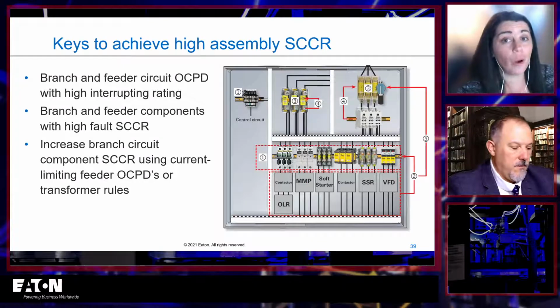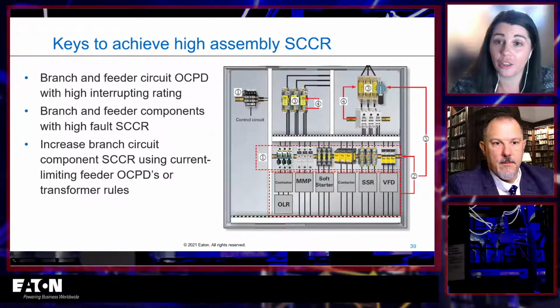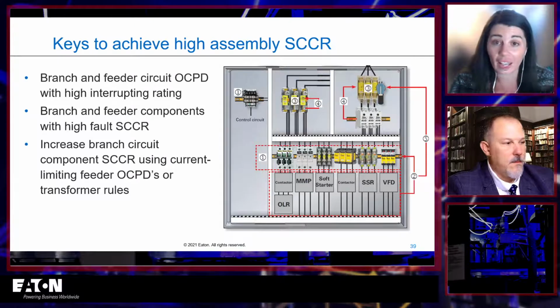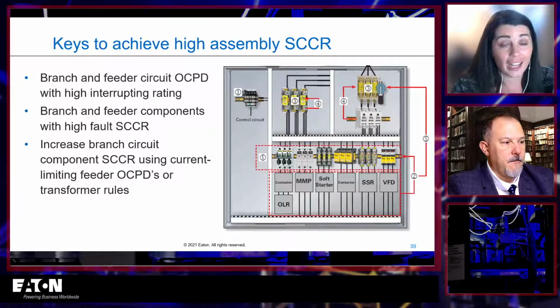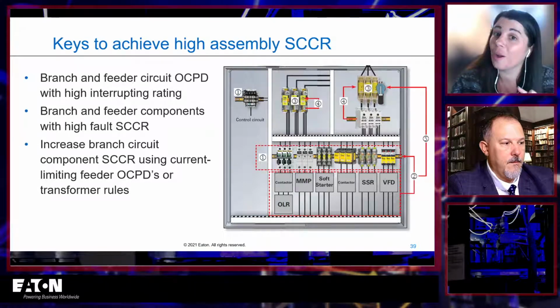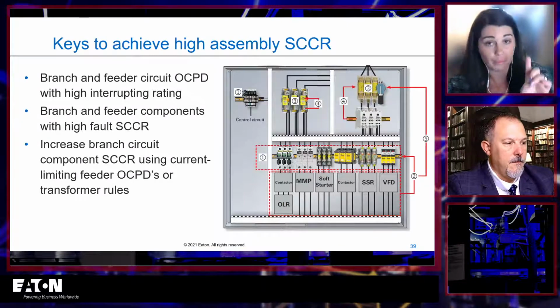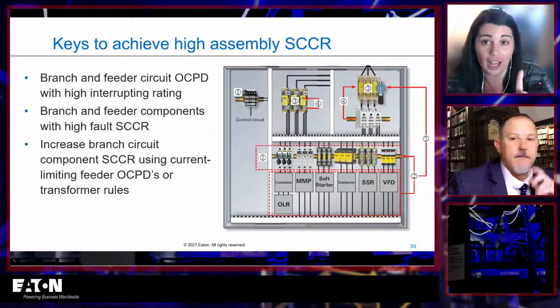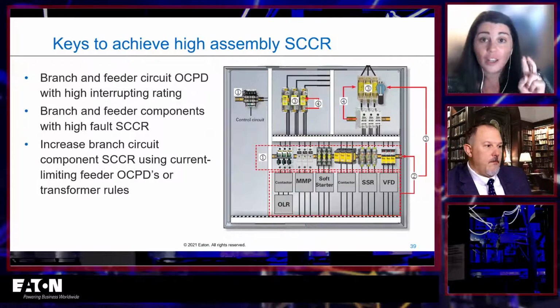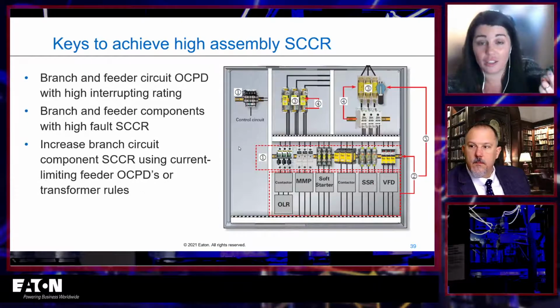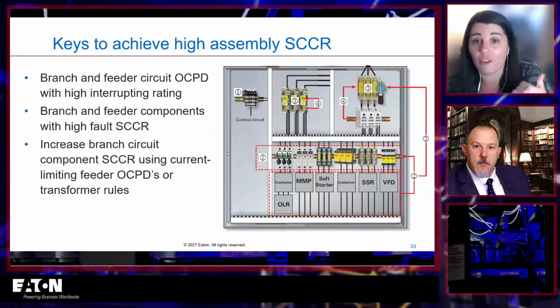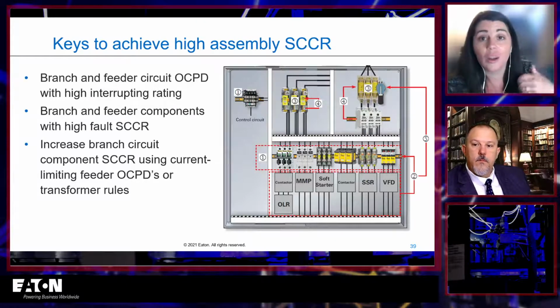So if I want to achieve a high assembly SCCR, there are really three main things you need to do. You need to have high interrupting ratings. You went through that process. There is no way for your short circuit current rating to be higher than your lowest interrupting rating. So you need high interrupting ratings, or at least an interrupting rating at your available fault current for that piece of equipment. So high interrupting ratings of your overcurrent protective devices. You want to have high short circuit current ratings too. You want those combinations. Use a combination rating, something that exists where you get that high fault rating.